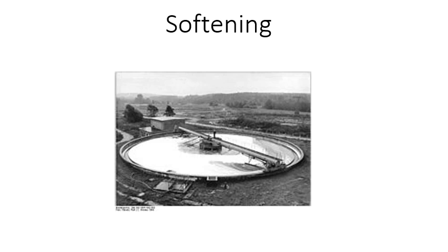Continue to raise the pH, and carbonate will turn into hydroxide at a pH of 11.3. At a pH of 11.3, all bicarbonate has been converted to carbonate, then to hydroxide forms. The calcium carbonate has precipitated, and what you'll be left with is magnesium hydroxide, which will now also precipitate.